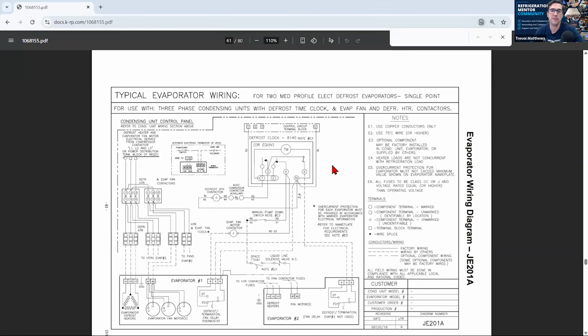So you have the standard 1, 2, 3, 4, N, X, and the timer, and the old school time clocks. You should actually be using a digital one. Most systems now will have the digital ones on there. You'll see Dixell or Carel or Eliwell, whoever it is, depending on where you're at in the world, they have defrost clocks built in. But this is an example where you have to go from one electrical wiring diagram to another one. This one's a typical evaporator wiring, where now it has the liquid line solenoid and the space thermostat, which you didn't see on the condensing unit side.